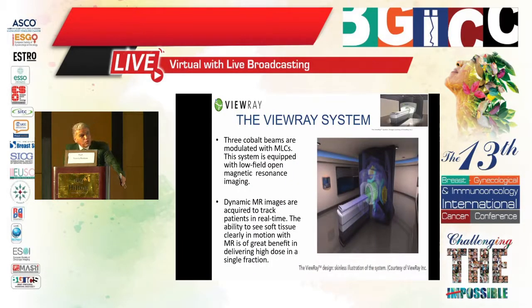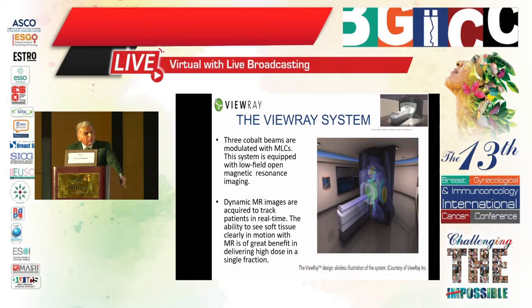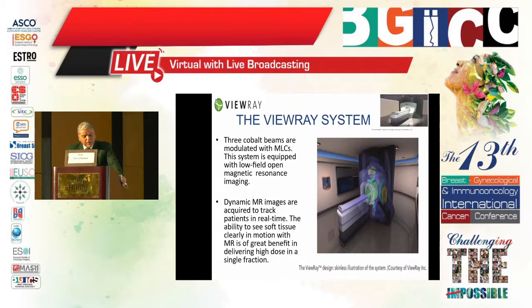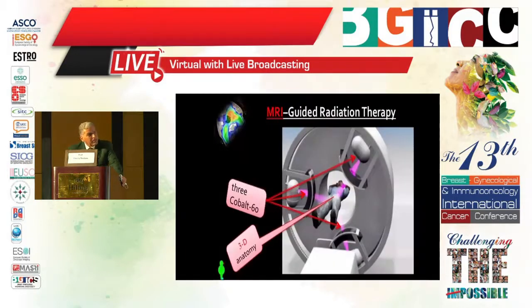Since three or four years ago we have had the ViewRay system, which uses three cobalt beams modulated by multi-leaf collimators. The system is equipped with a low-field open MRI. This was the first machine to use MRI during radiotherapy for patient positioning verification. Dynamic MR images are acquired to track the patient in real time, and the ability to visualize soft tissues in motion is of great benefit in delivering high dose in a single fraction. I hope we will see this machine in Egypt soon.